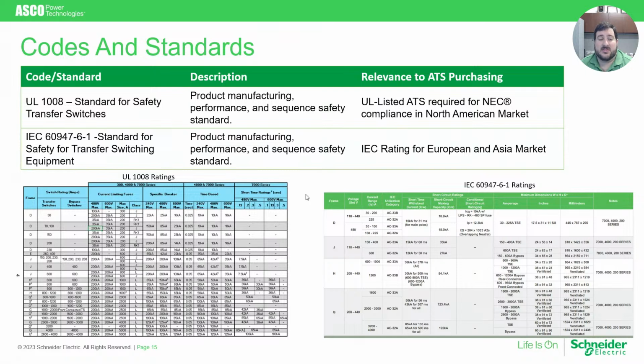Today, I'm going to mention two standards that are critical to understand in this space, which are the UL 1008 standard, which is the NEMA and primarily North American standard used for denoting the performance requirements and manufacturing requirements for a transfer switch. As well as IEC 60947-6-1, which is very similar to UL 1008 in the sense that it is the product performance and manufacturing standard for what started in the European market and has then expanded to other regions globally as the standard.